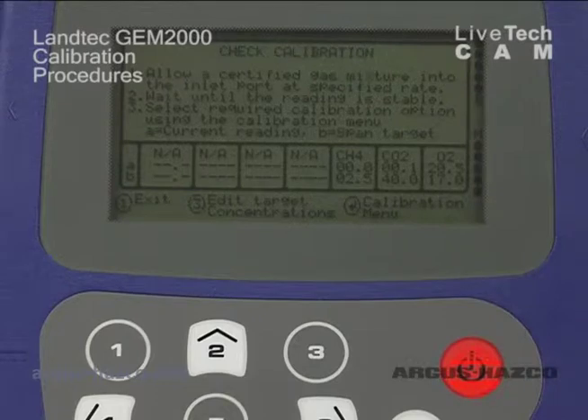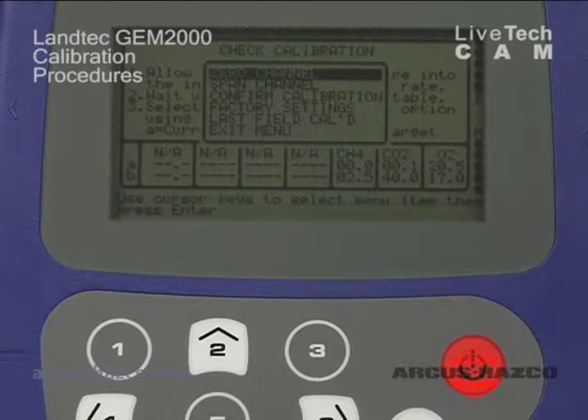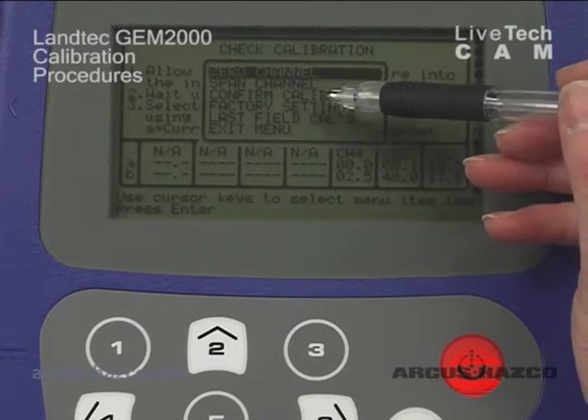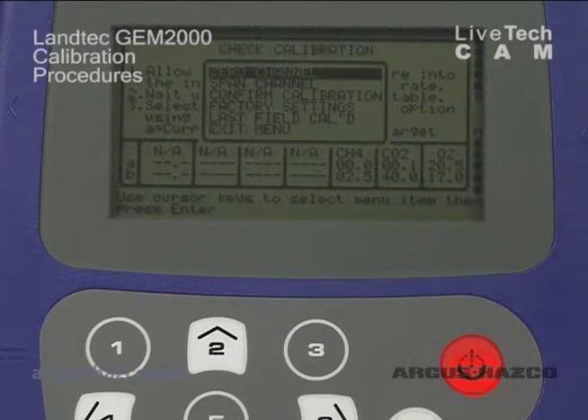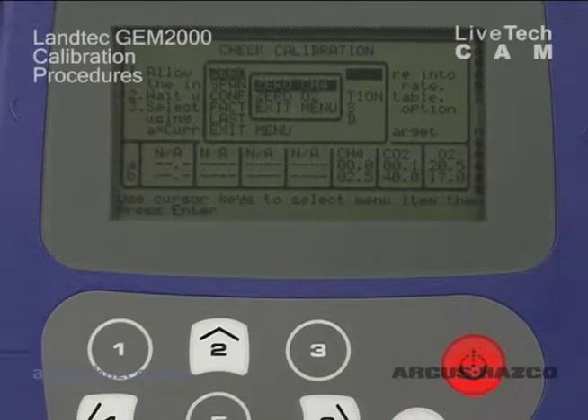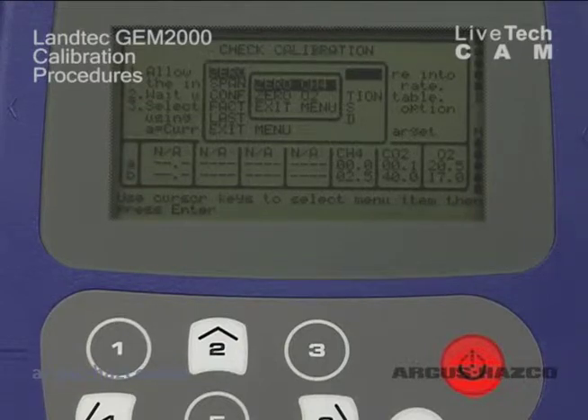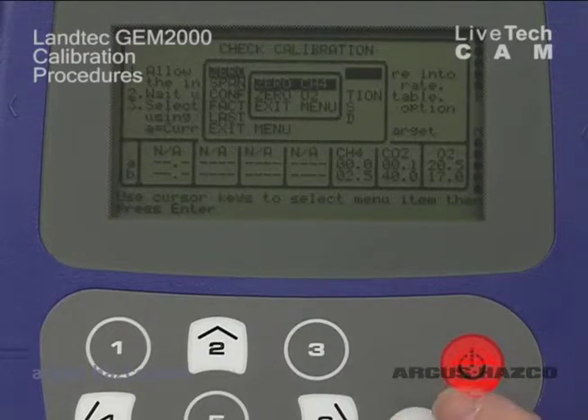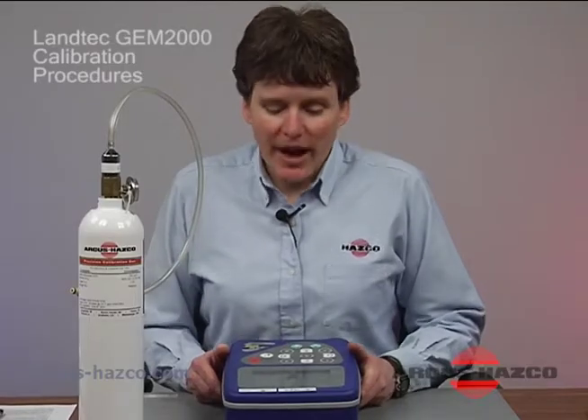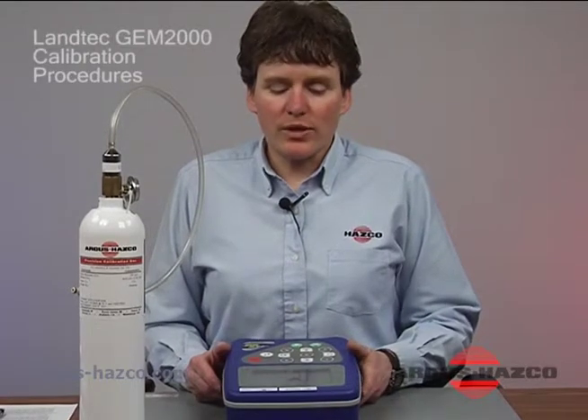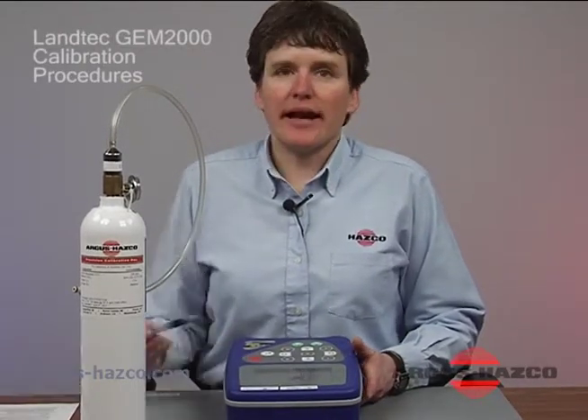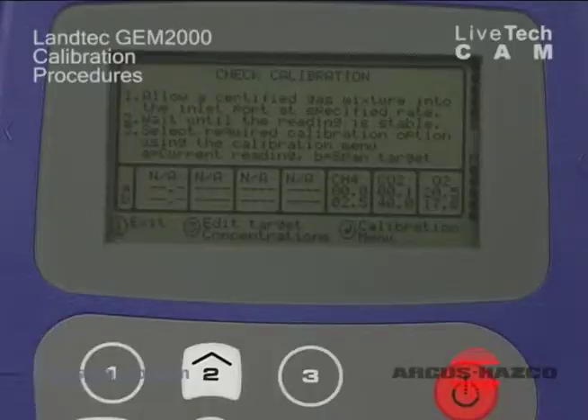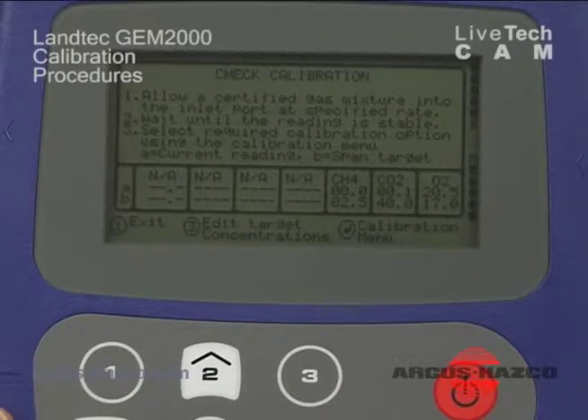So for our calibration menu, we hit Enter, and we have our submenu pop up. And again, we have 0 channel or span channel. And you always want to 0 your channels first, so I select that. I hit Enter. And I'm going to go ahead and just do the CH4, the methane. And we are in clean ambient air. To actually start calibrating the unit then, before we enter into our calibration menu by hitting the Enter key, we want to go ahead and turn on our fan, our pump.